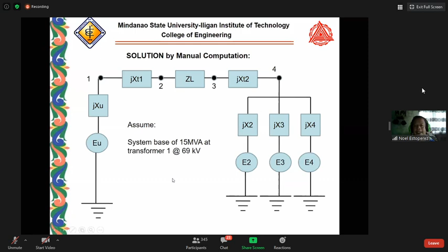Okay, for the utility impedance, as we all know, for the fault level, it is given with a short circuit MVA of 535. The MVA base is 15. So we have here 0.028 per unit. This is important. Then the transformer XT1 will be 0.0694 after computation. And for transformer 2, we have 0.228.